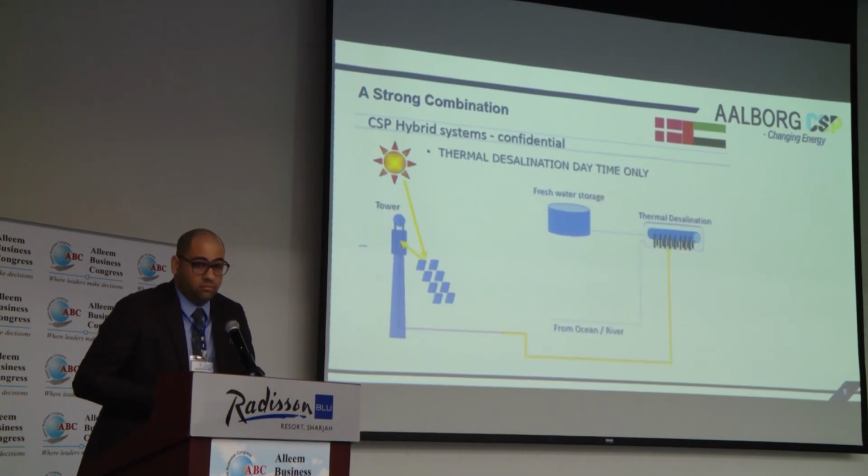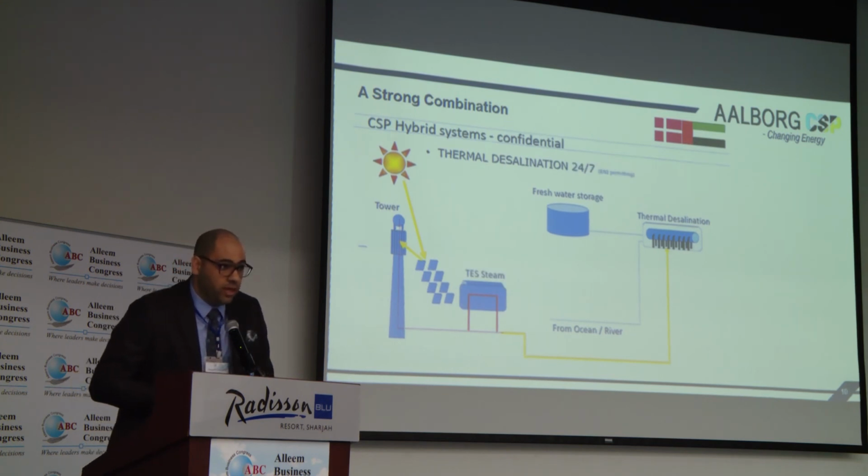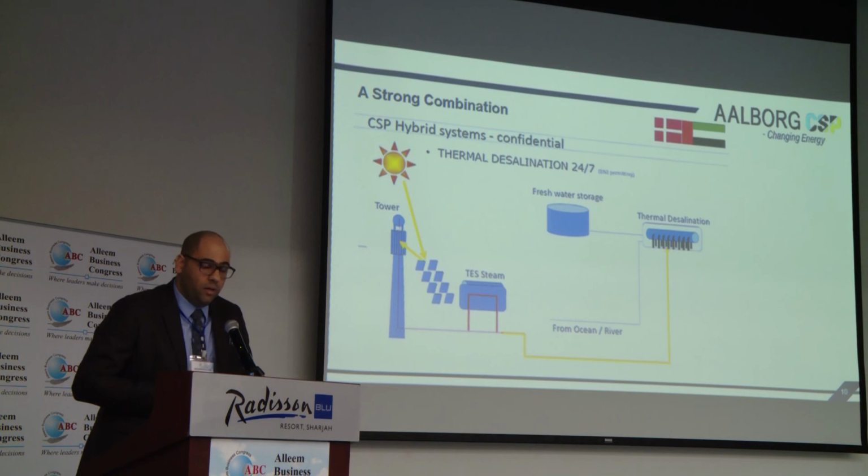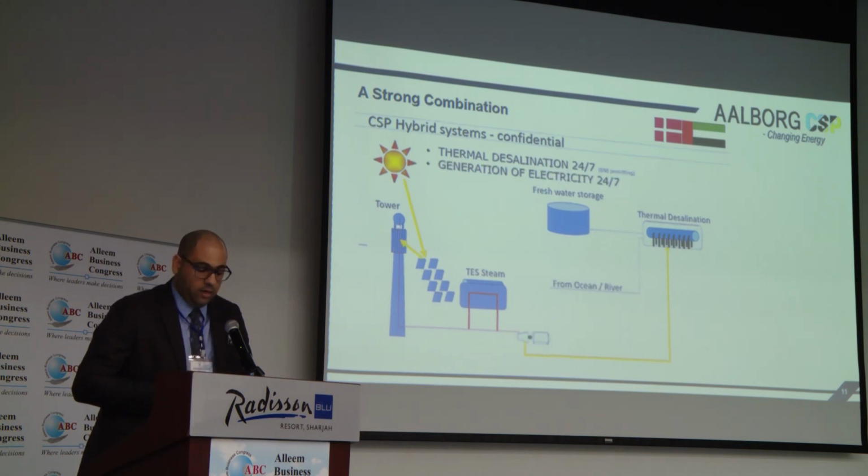Here comes the solar thermal solution, and this is also a layout with solar tower technology. We are desalinating using multiple effect distillation, MED, also known as thermal desalination. This is also only during the daytime because there is no storage. But when we add storage, we can guarantee 24/7 desalination. To make a stronger, more effective and efficient combination, you can even make hybrid systems of those. Here, you can even produce electricity, and you don't have waste, because the waste heat or waste steam is condensed and then utilized to desalinate the water.